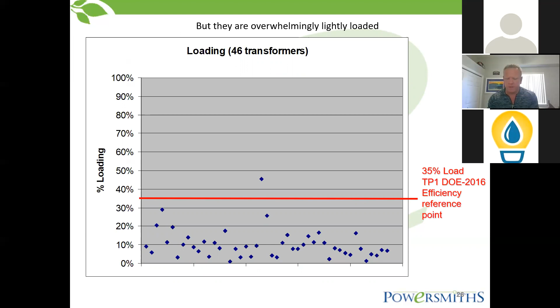So what I did is I just took two of them and did an example. You've got two schools, both at 75 kVA. One's at 3.3% loading, the other's at 3.2% loading. You see the efficiency difference between the two of them. This is two different transformers at two different schools, but same loading profiles. So just that particular transformer is about $1,000 per year that they're saving if they just replace it. Through the life of a project, the life expectancy of that transformer, that is substantial enough to look at.